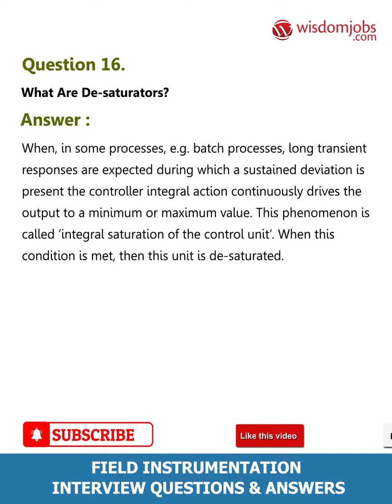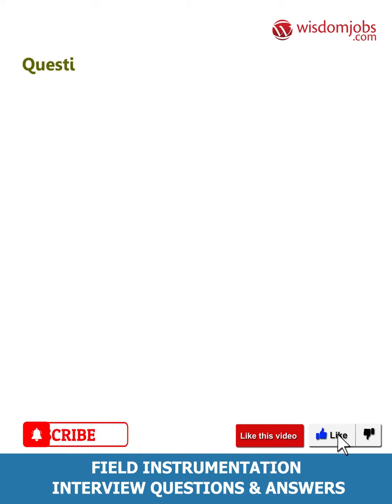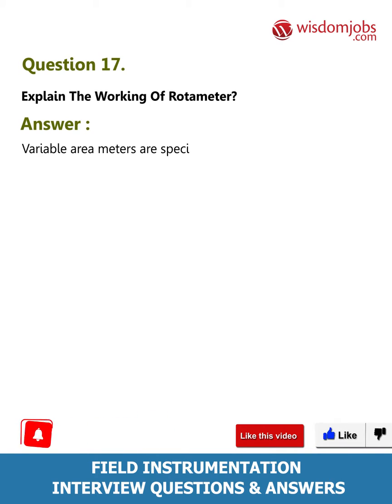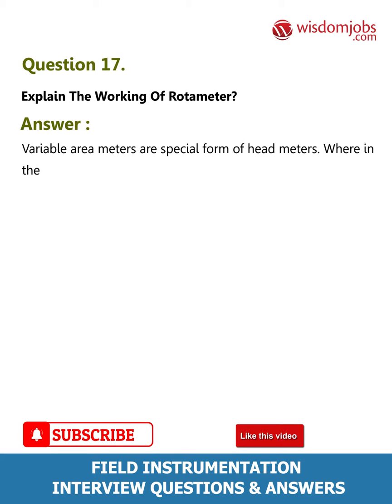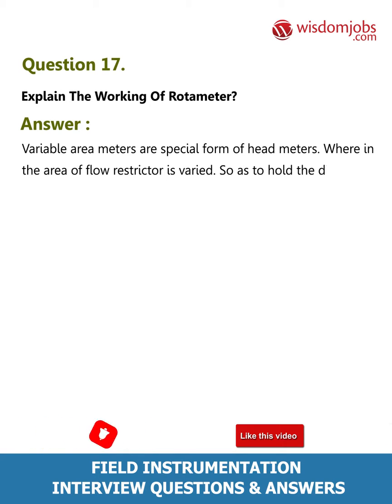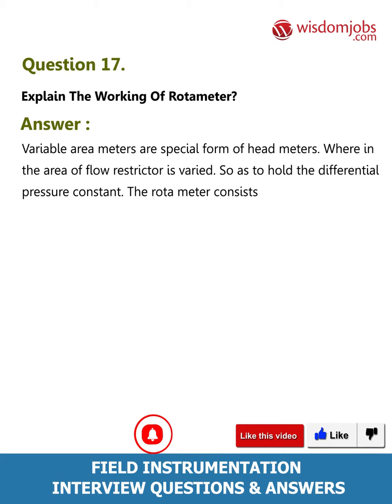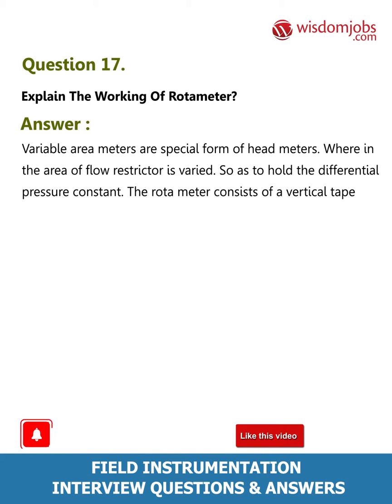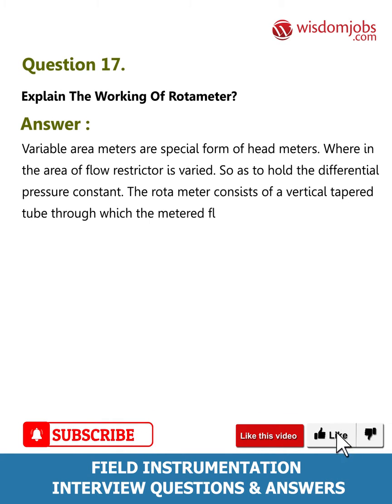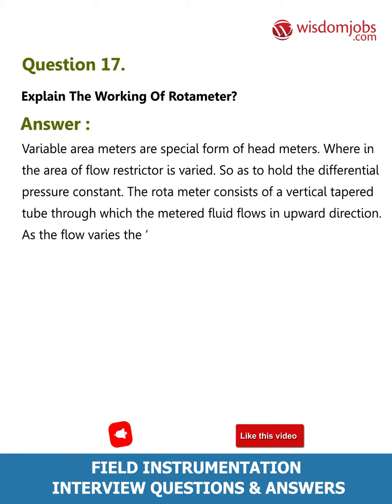Question 17: Explain the working of a rotameter. Answer: Variable area meters are a special form of head meters wherein the area of the flow restrictor is varied so as to hold the differential pressure constant. The rotameter consists of a vertical tapered tube through which the metered fluid flows in an upward direction. As the flow varies, the float rises or falls.